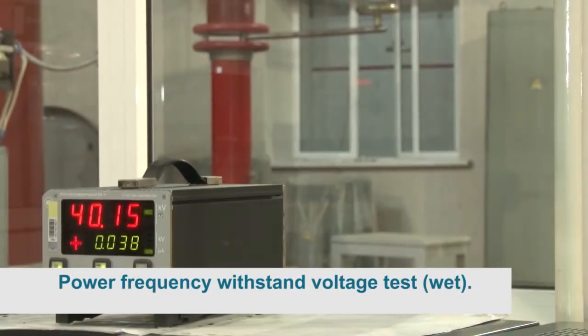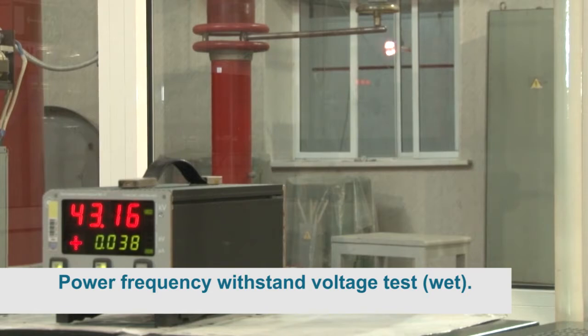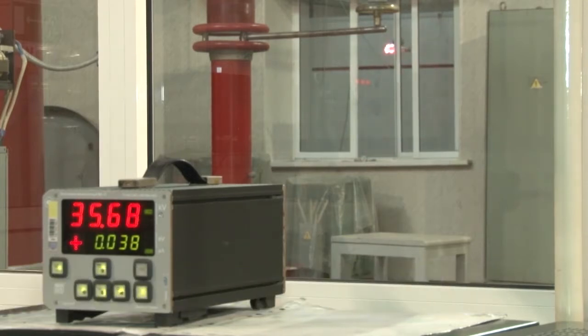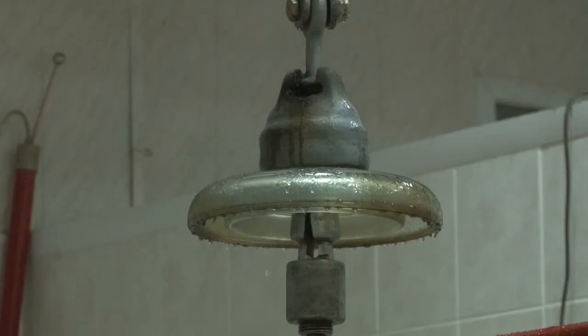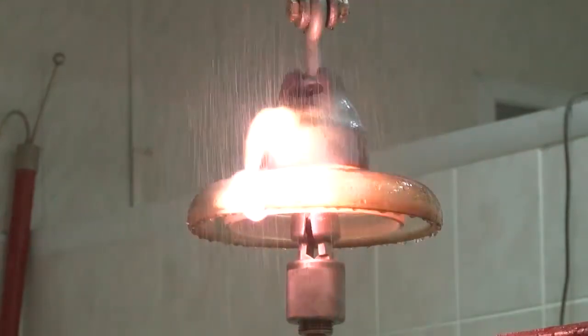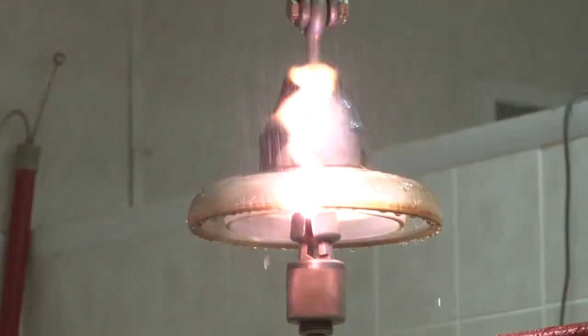Power frequency withstand voltage test, wet. The test was administered by application of standard voltage to the insulators. Test voltage for the insulator of PS12A was 45 kilovolts. Application of voltage continued for 1 minute. The insulator didn't pass the test. The puncture occurred at the level of 40.1 kilovolts voltage. Insulators of type PS12A do not meet the IEC requirements.